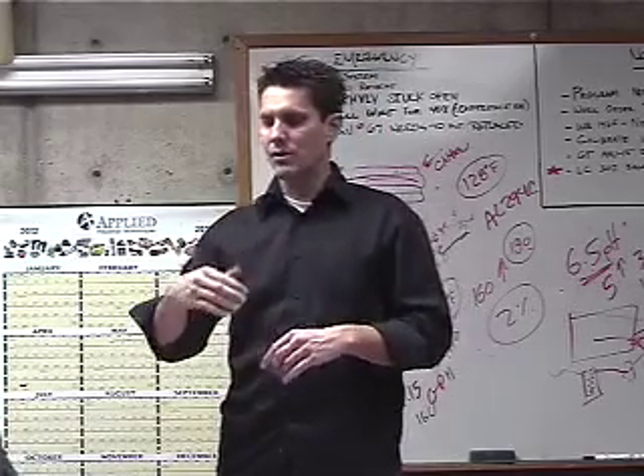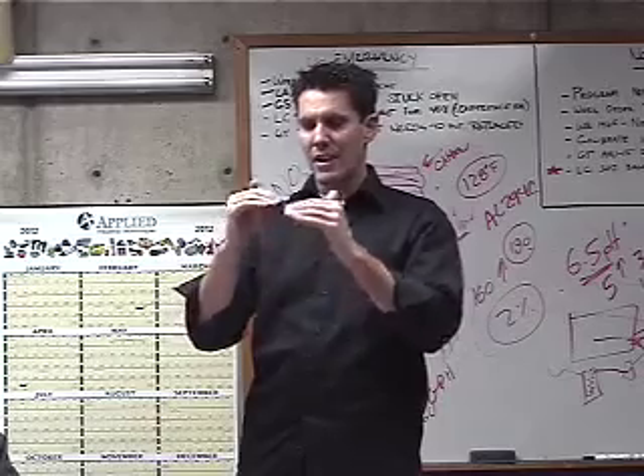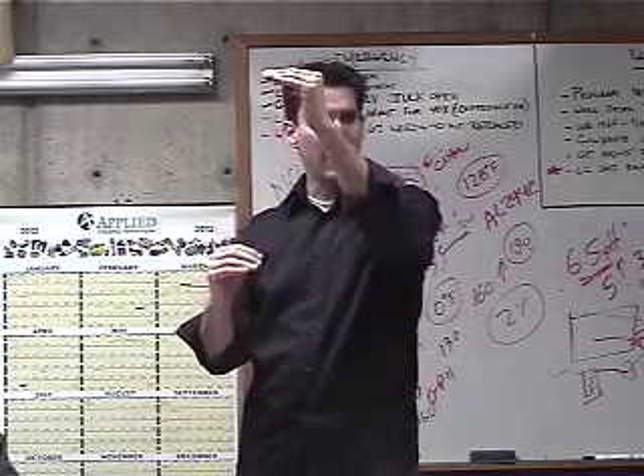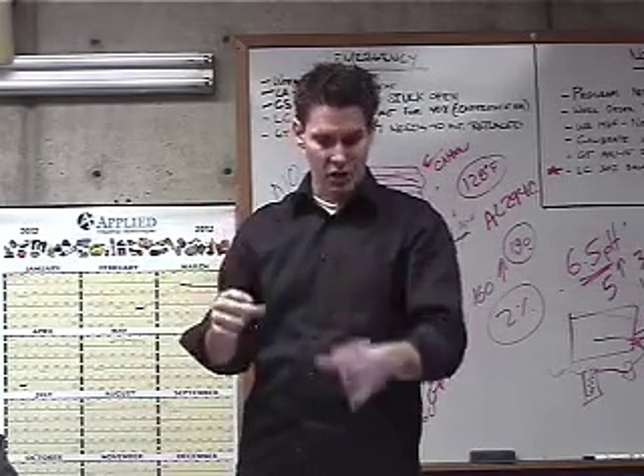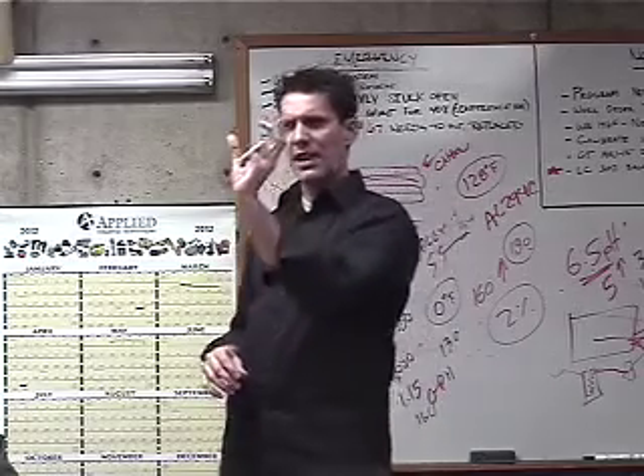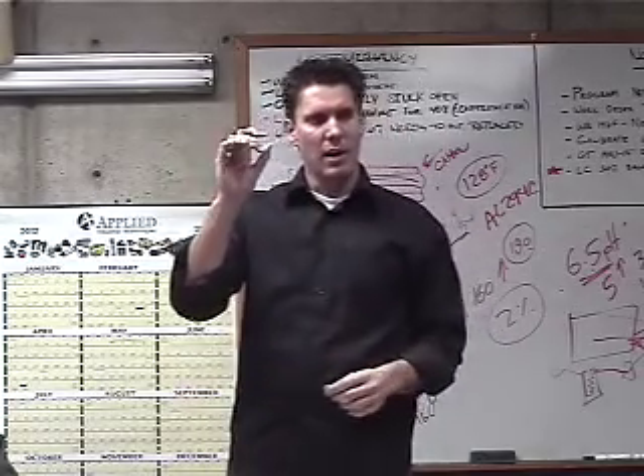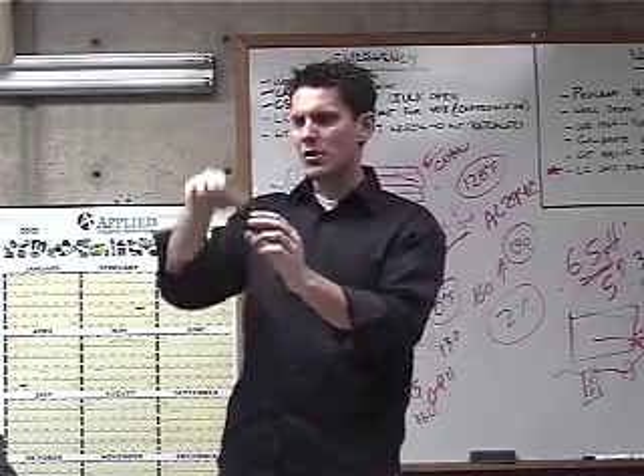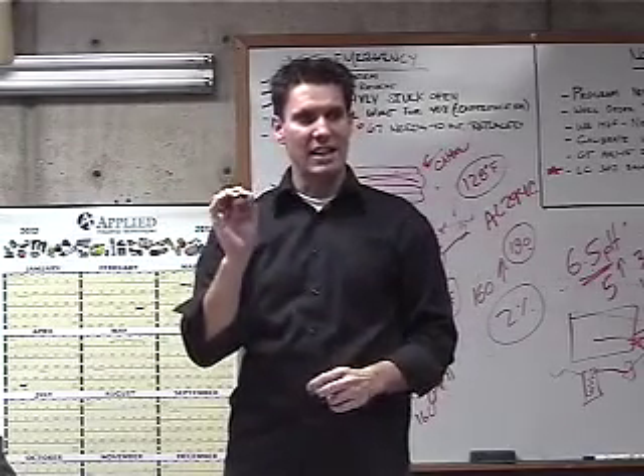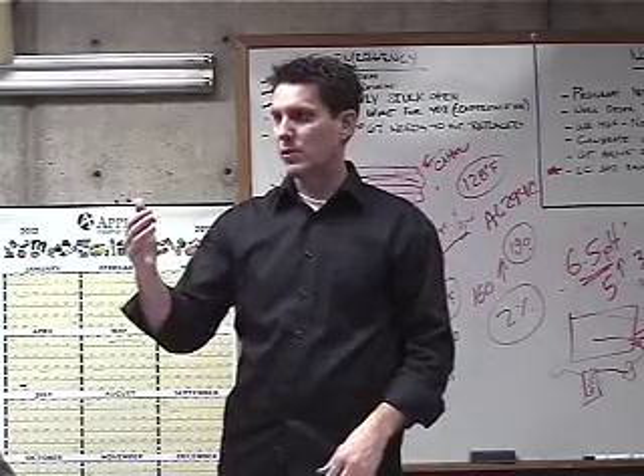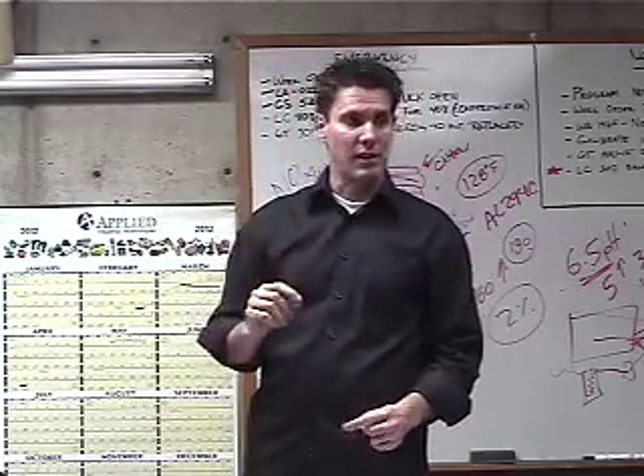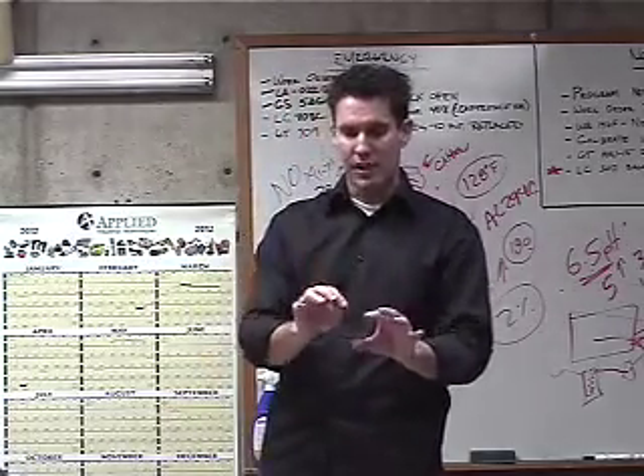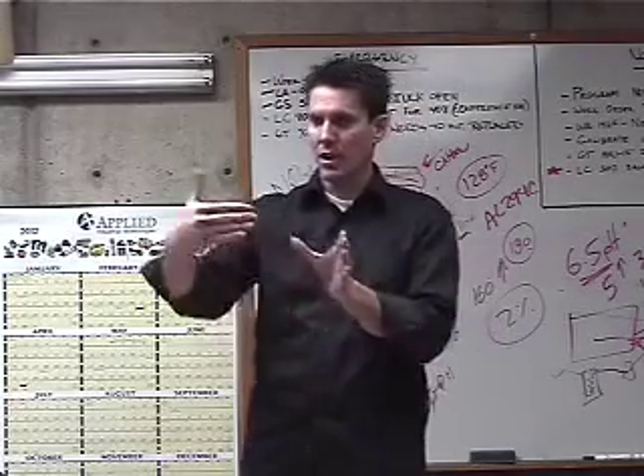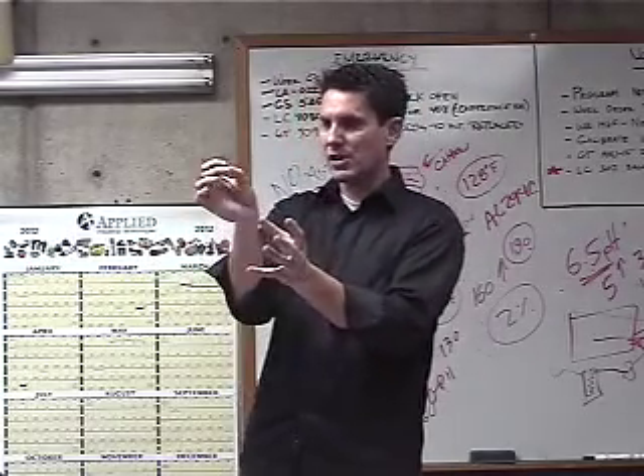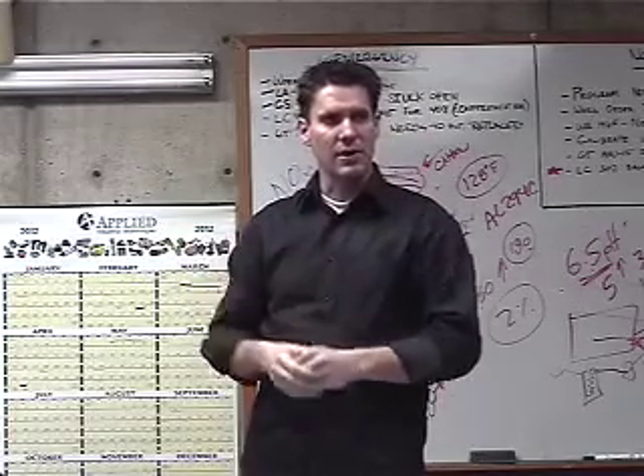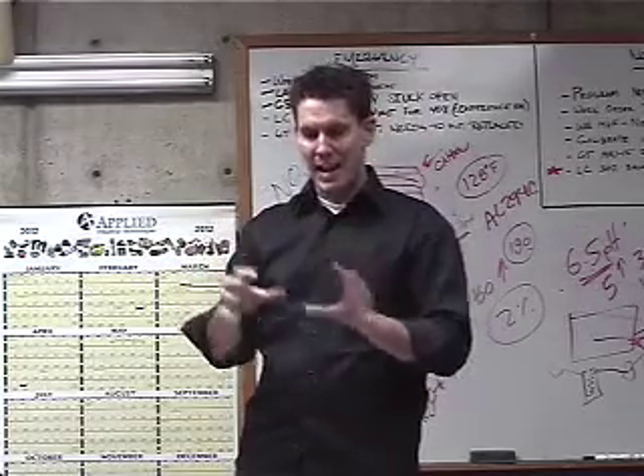And then you can get into, as the boiler's firing, the 10 points, low fire to high fire, and the 8 points in between, where you can set up your combustion and make the adjustments that you need. So as you're standing there watching the boiler operate, you look down that viewport. As you watch the boiler modulate, if during that modulation range the flame looks any different than it's supposed to look, then that's when you know we better get in and check all of this. And as you program these different percentages for the air servo valve and the gas servo valve, you're changing the position on these valves, and you actually see them change as you increase or decrease the numbers. And so you're programming that in.